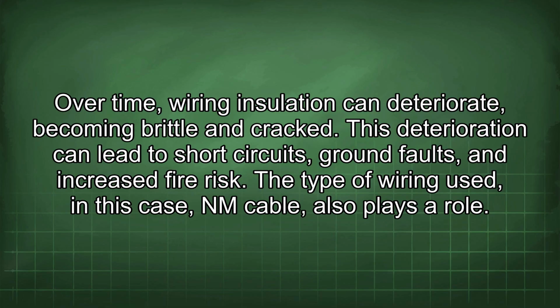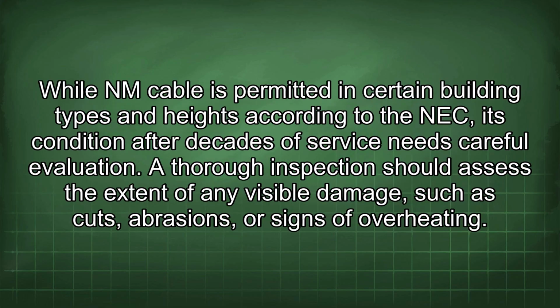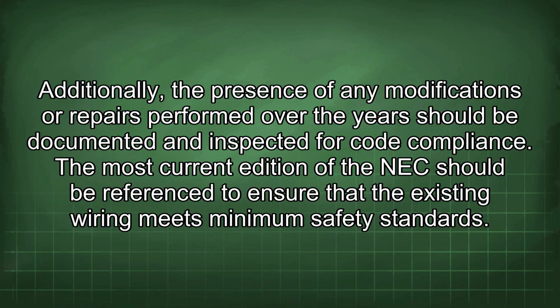Over time, wiring insulation can deteriorate, becoming brittle and cracked. This deterioration can lead to short circuits, ground faults, and increased fire risk. The type of wiring used, in this case NM cable, also plays a role. While NM cable is permitted in certain building types and heights according to the NEC, its condition after decades of service needs careful evaluation. A thorough inspection should assess the extent of any visible damage, such as cuts, abrasions, or signs of overheating.